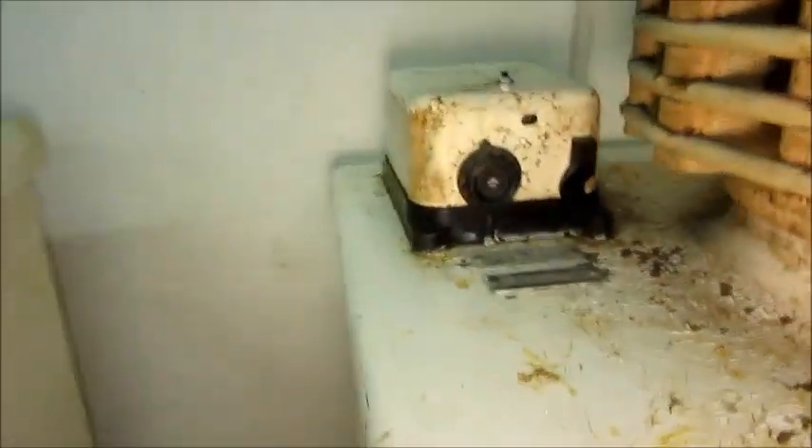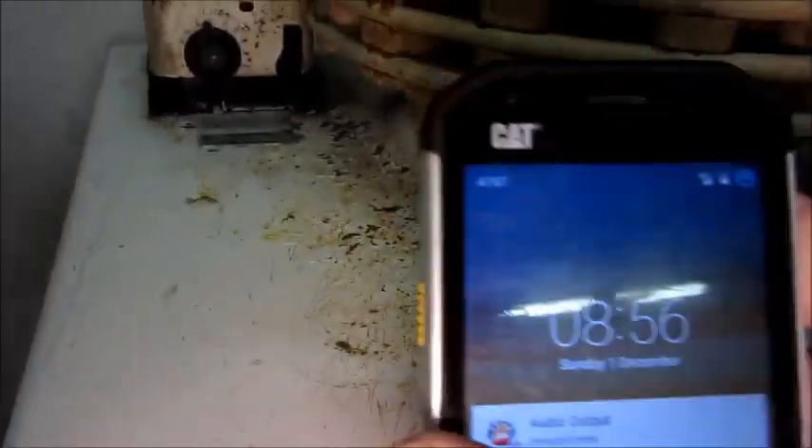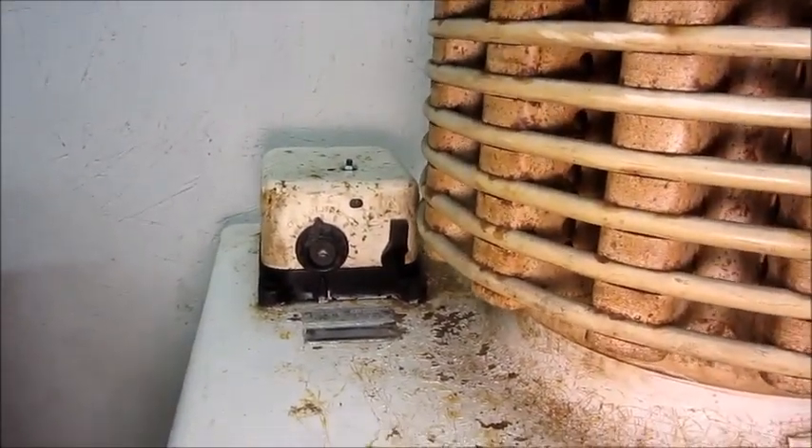So I'm going to plug it in and give it some time for the heater to work before I start it. The machine is off other than the heater, which is always active — you can see the 'off' indicator. I'm going to give it about four hours. Right now it's about 9 a.m., so probably after lunch I'll start it up and we'll see how it sounds and how long it takes to start cooling.